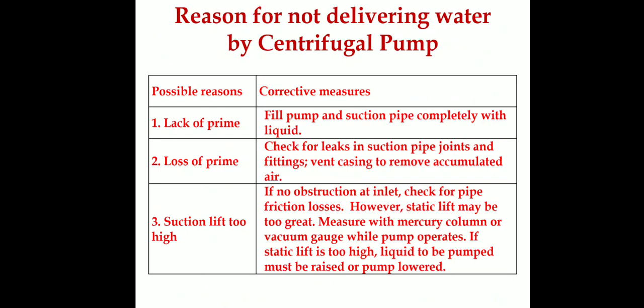The second reason is loss of prime. If the suction line has a leak, or if the foot valve leaks, that will cause loss of prime. Rectifying the leaking foot valve or suction line will resolve this issue.